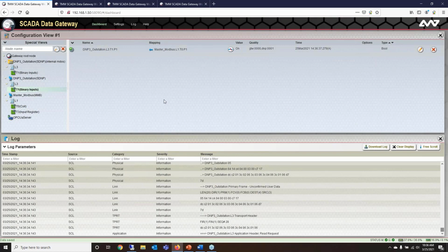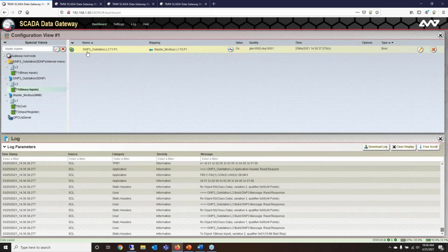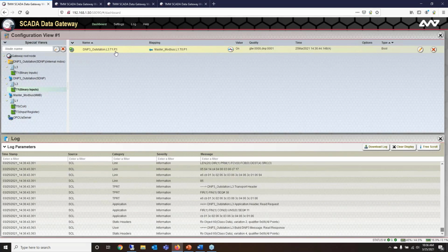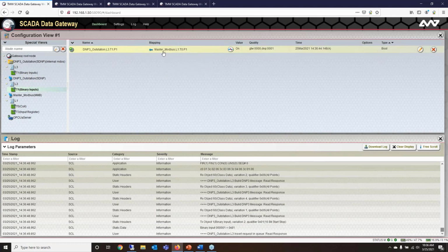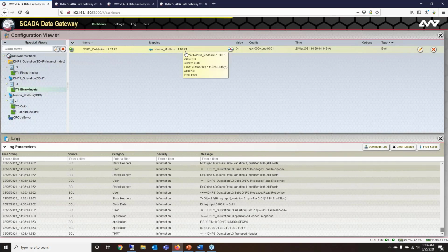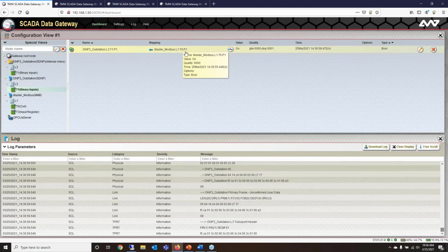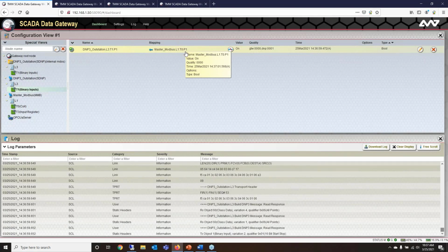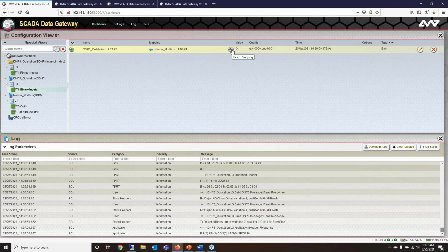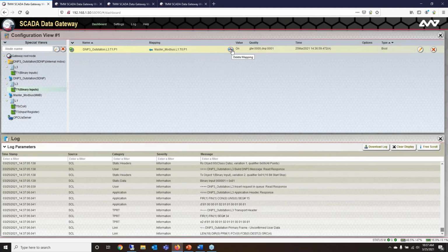So if I hit OK here, you'll see I now have a DNP3 outstation point. It is T1 P1, where T1 is just a binary input. You can see right next to it that we are mapping it from the Modbus master from its T0 P1. If I make a mistake and this wasn't the point I wanted to map, or I need to remove a mapping, you can click this button here and it will delete any mapping and let you start back over.